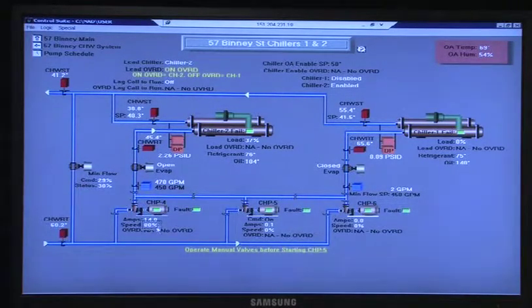Right now, pump number 4 is on. Water's coming up through and is pressurized across to here, but that's closed. That's the evaporator valve, which is controlled by the chiller. It's telling it to close. This one's open, and chilled water is coming up through here. You see these valves here? Very important. Each chiller requires minimum flow values.